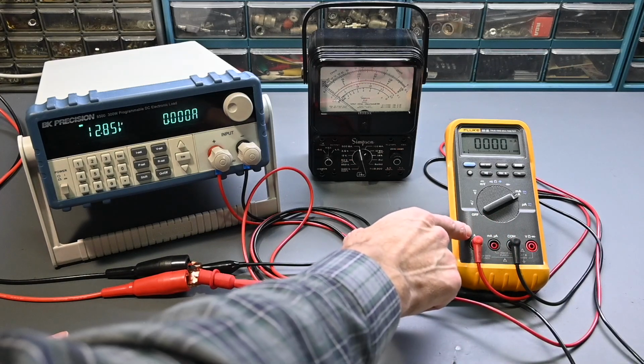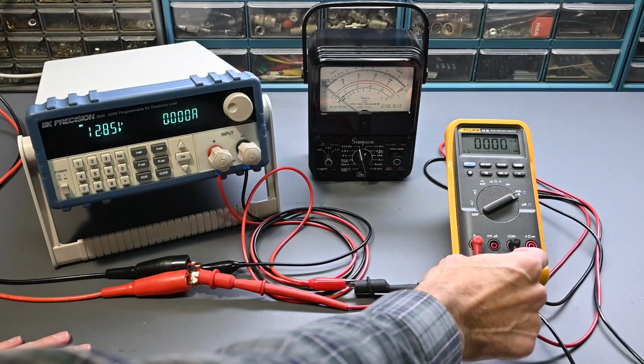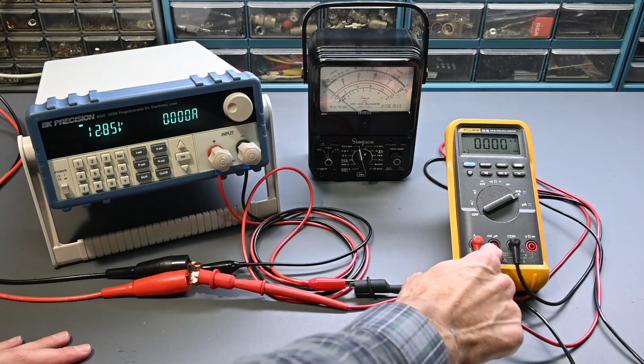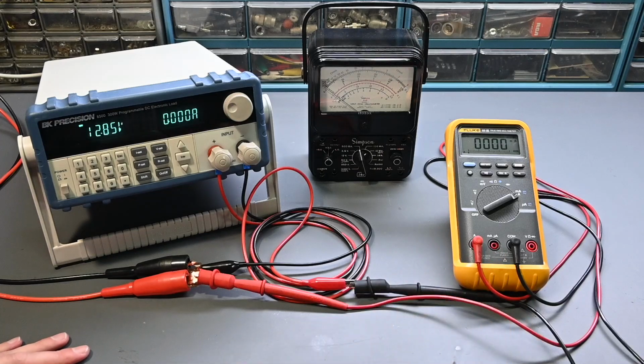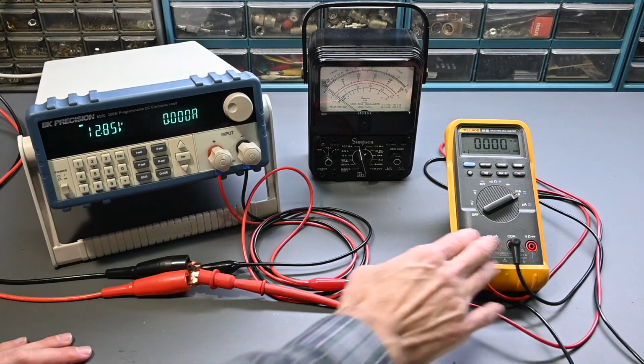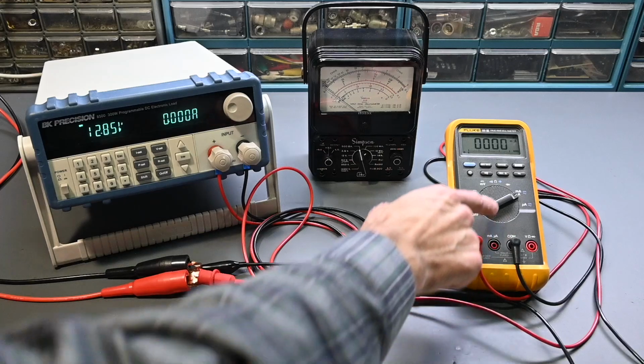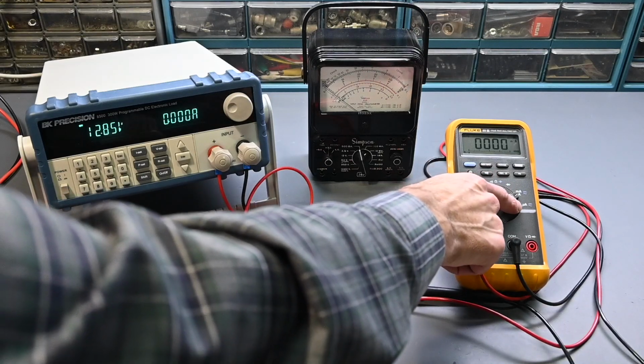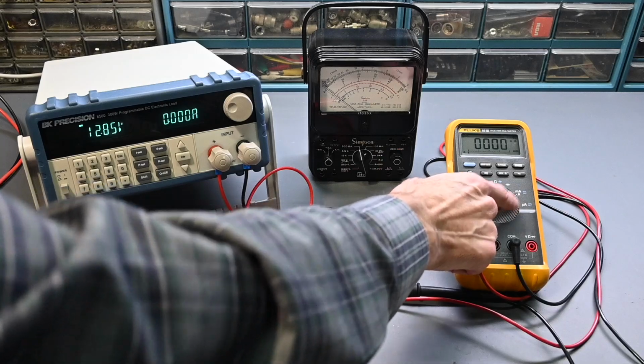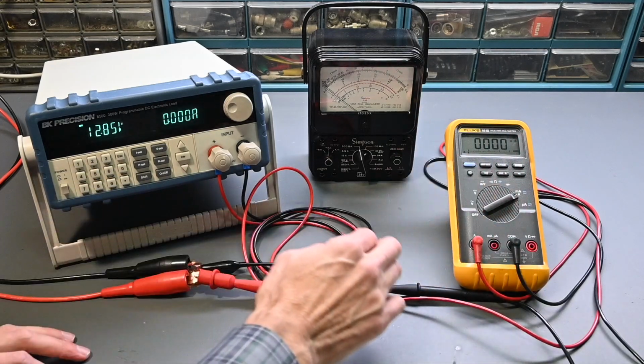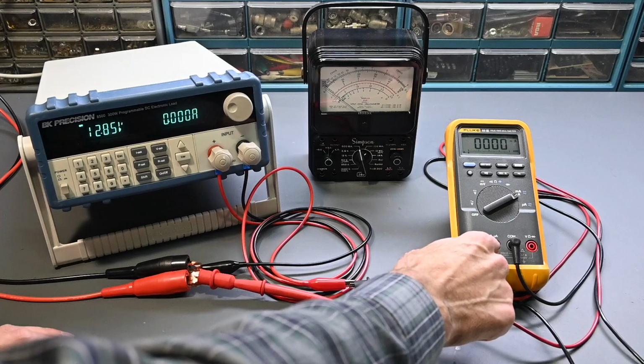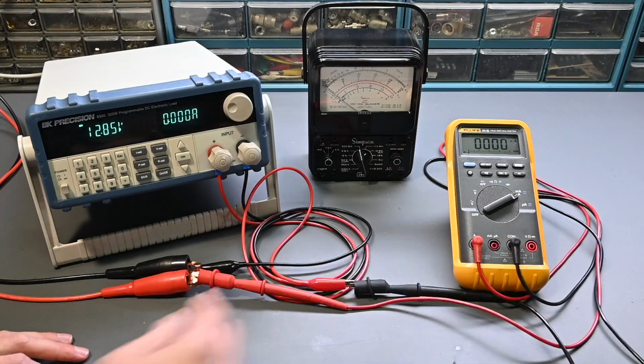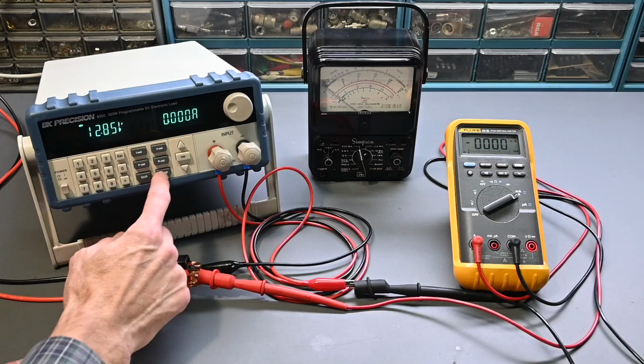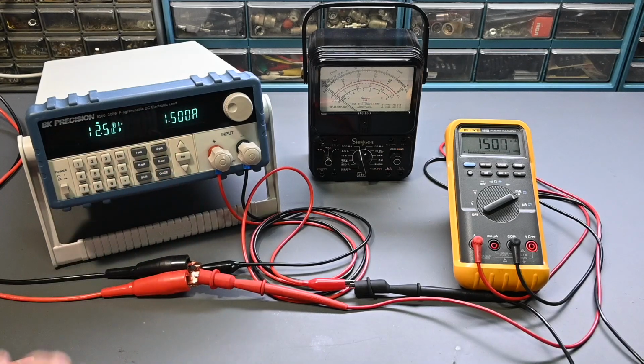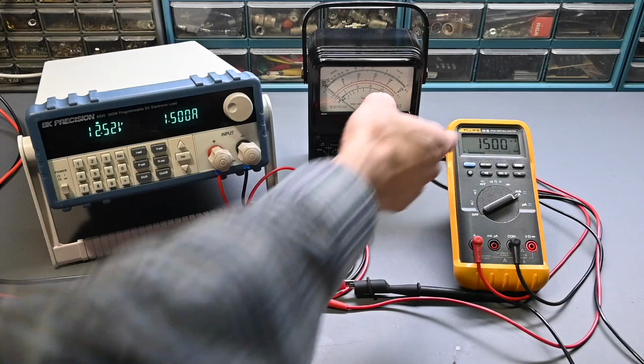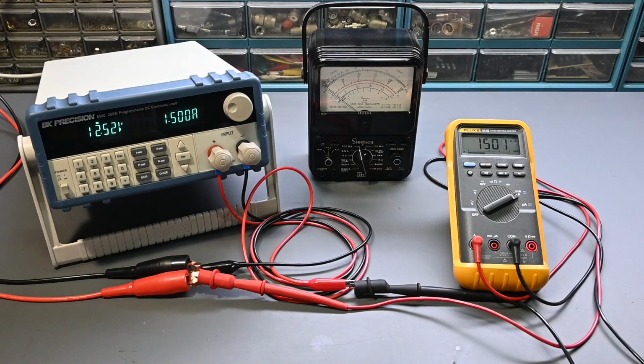So in this case, on the amps setting, from amps to common is fused at 10 amps, and from the milliamps and microamps jack right here over to common is fused at just 400 milliamps. So again, choose the appropriate range. I have it set here on the 10 amp setting, of course, and then over here it's on the milliamp and amp setting, not microamps. If this is set to the wrong position, you'll just get an overload indication. It won't actually hurt the meter, but it will blow the fuse if you have this on the wrong setting, in the wrong jack, and too much current flows. Okay, so I'll turn this back on again. So you can see 1.5 amps right there, and 1500 milliamps or 1.5 amps. So perfect, just that simple to measure current.